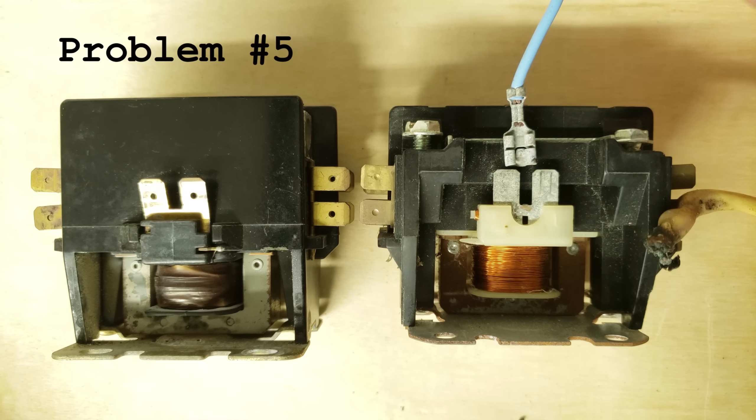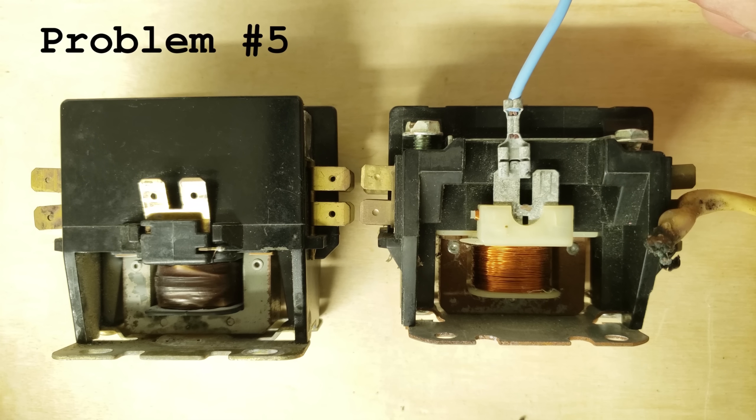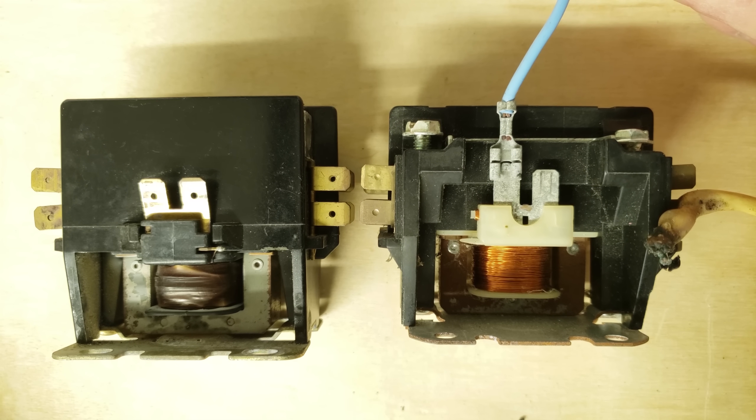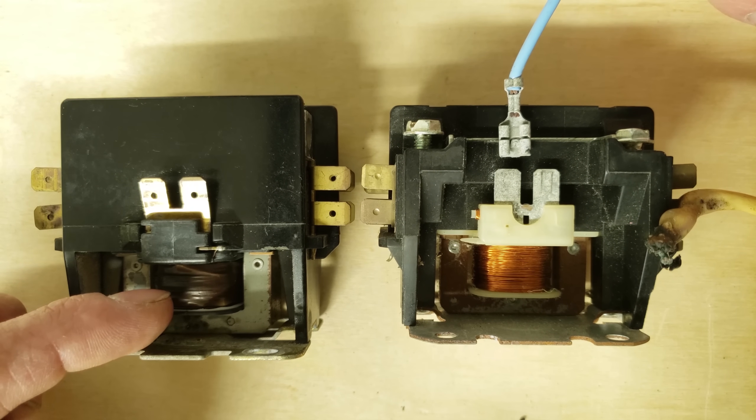Problem number five could be a bad or loose electrical connection or improper voltage going to the contactor coil. Say you have a corroded electrical connection here, then you're gonna get a lower voltage than desired on that contactor coil. You could end up having the result of a burnout contactor coil such as this right here.